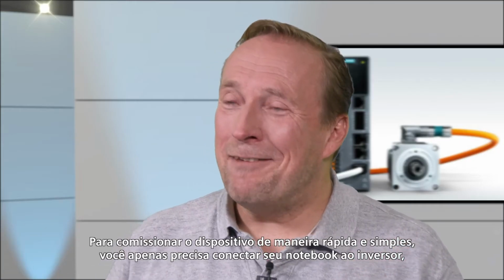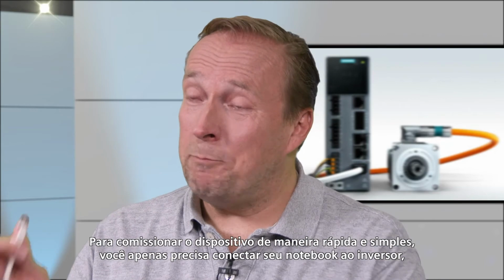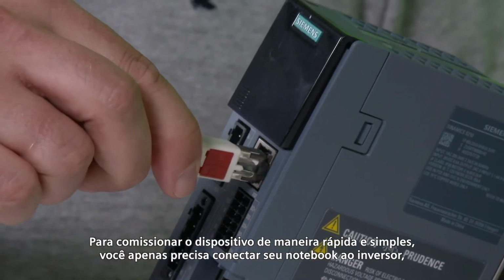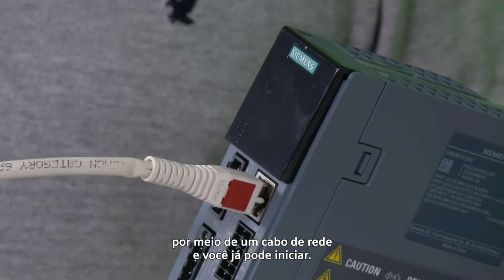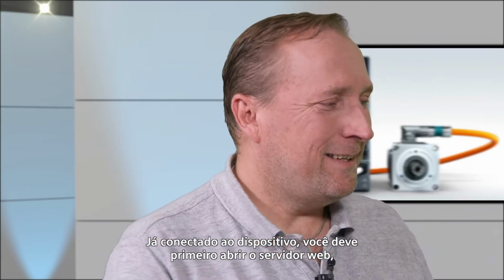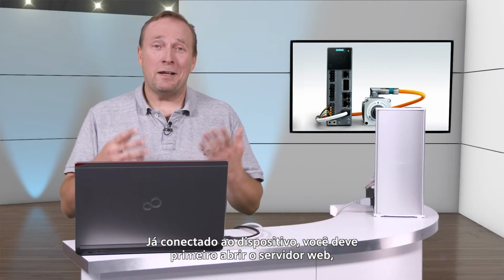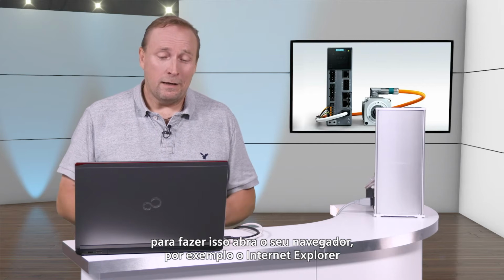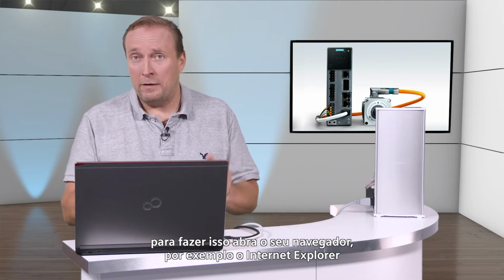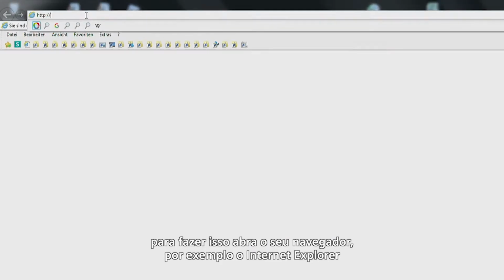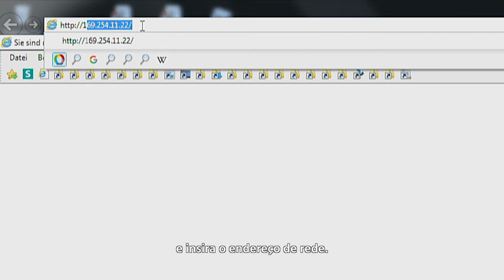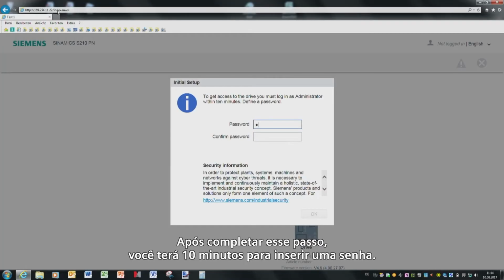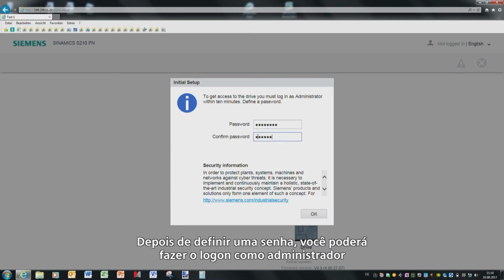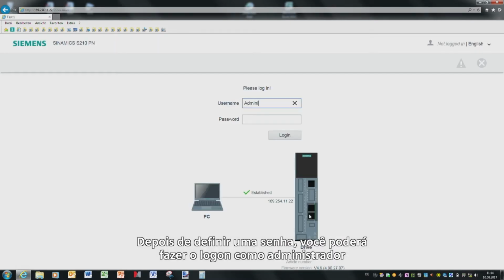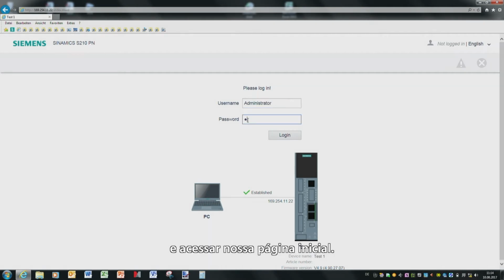To commission the device quickly and simply, you just have to connect your laptop to the converter using the LAN cable, and you can already start. Having established the connection to the device, you must first open the web server. To do this, go into your browser, for example, Internet Explorer, and enter the internet address. Having completed this step, you have 10 minutes to enter a password. And once you have assigned and entered a password, you can log on as administrator and access our start page.